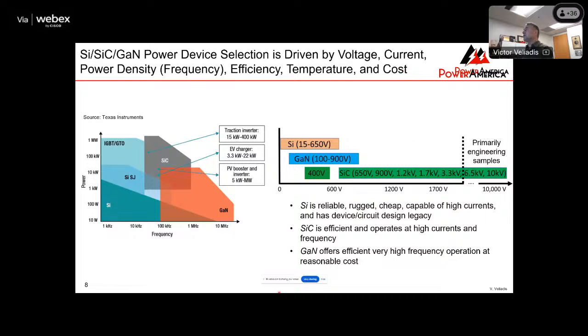So if you look at this graph right here, you will see that silicon carbide is basically available at 650, 900, 1.2 kV, 1.7, and 3.3 kV. These are all products available on the market today, while 6.5 and 10 kV devices have been successfully demonstrated.